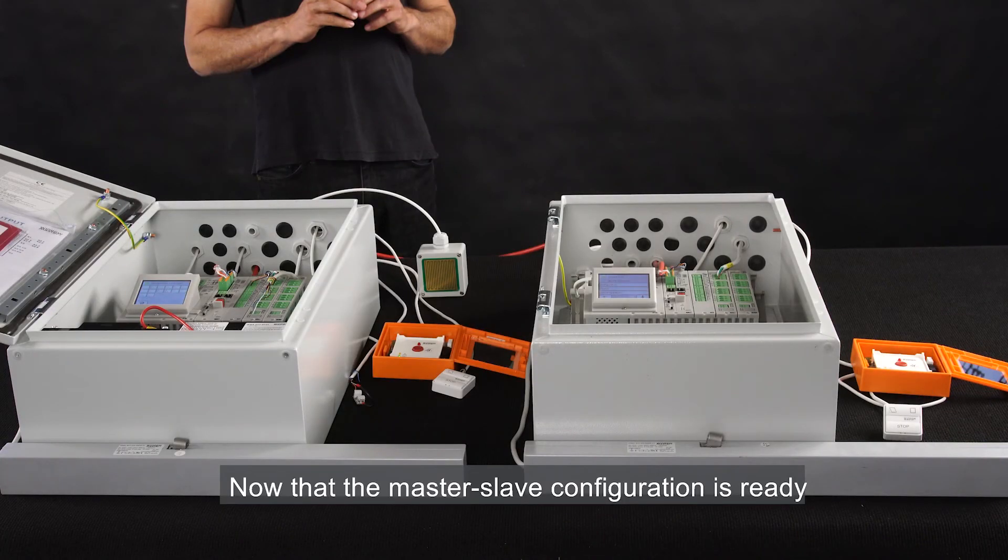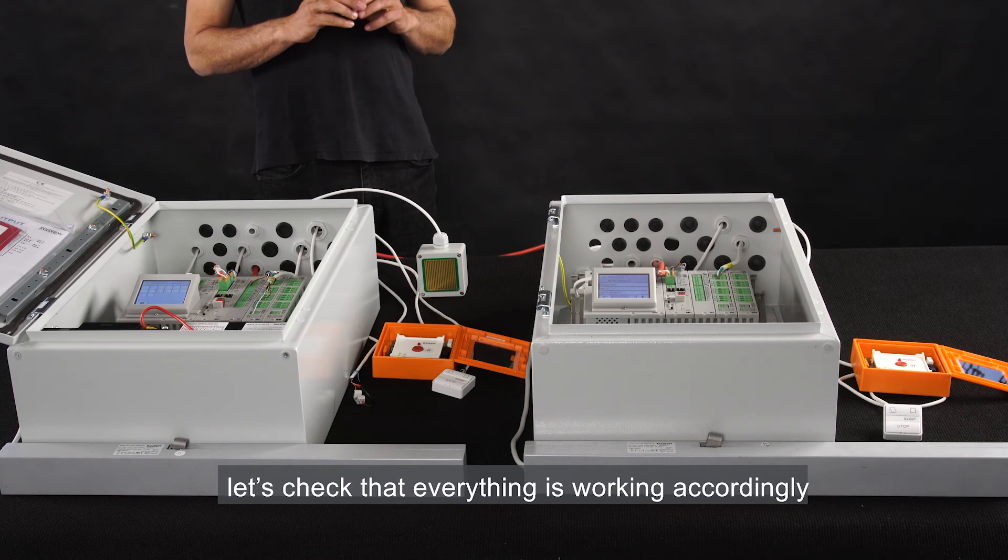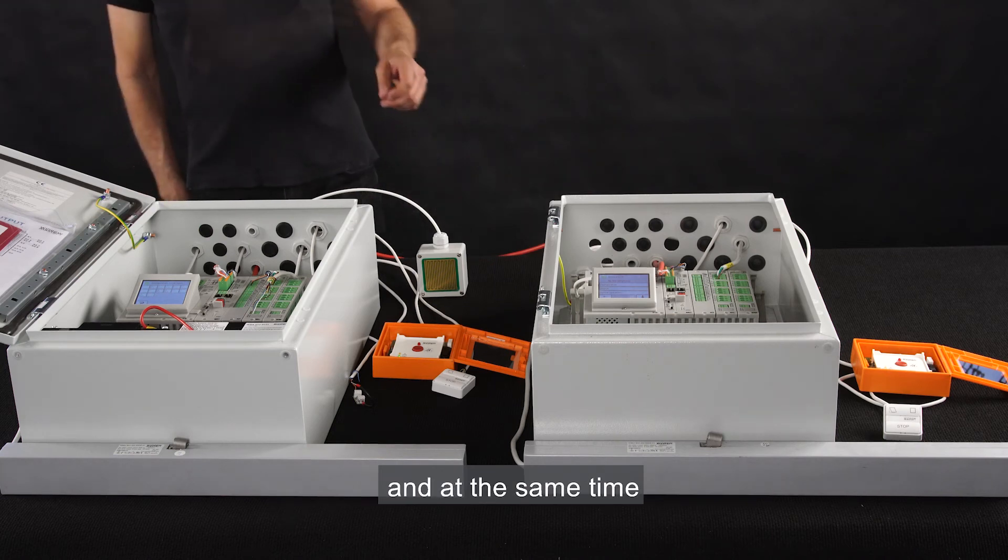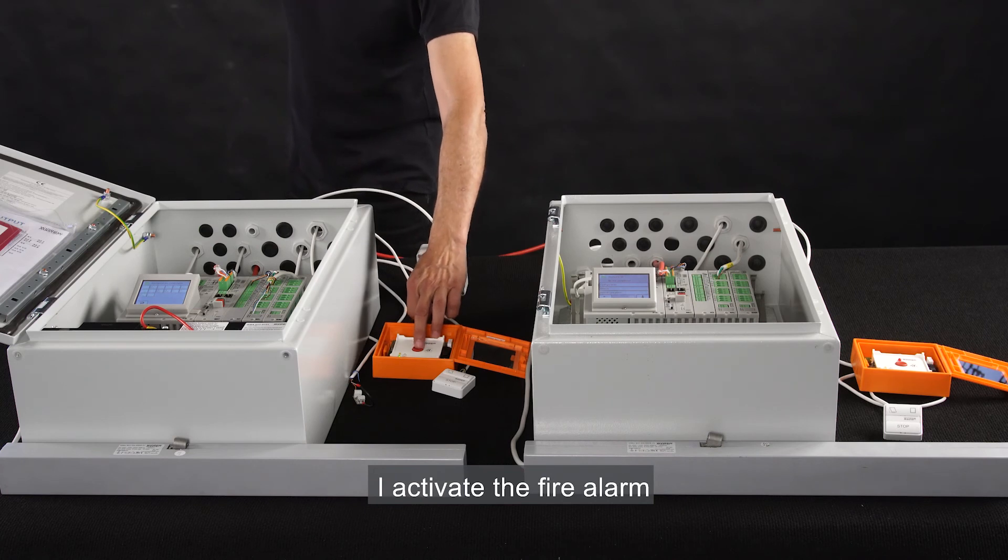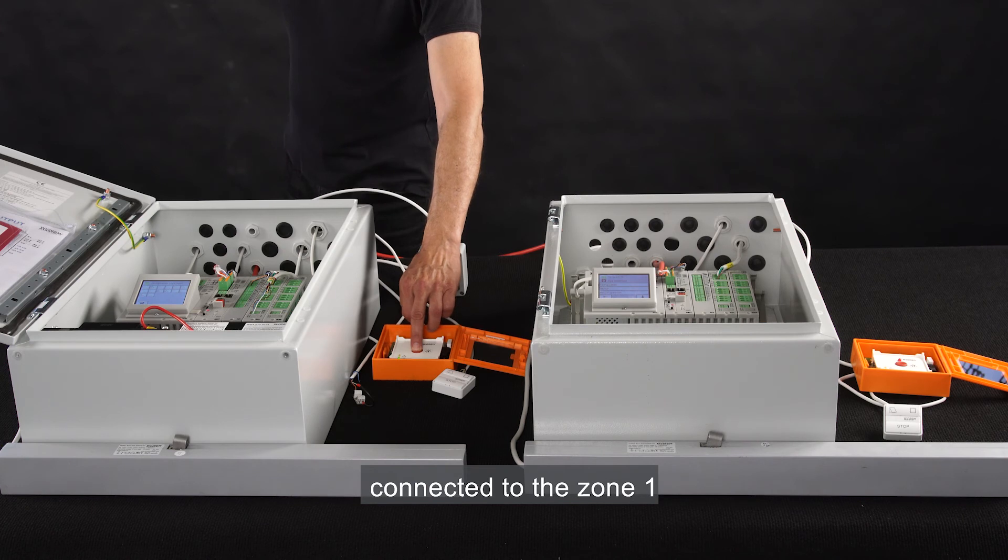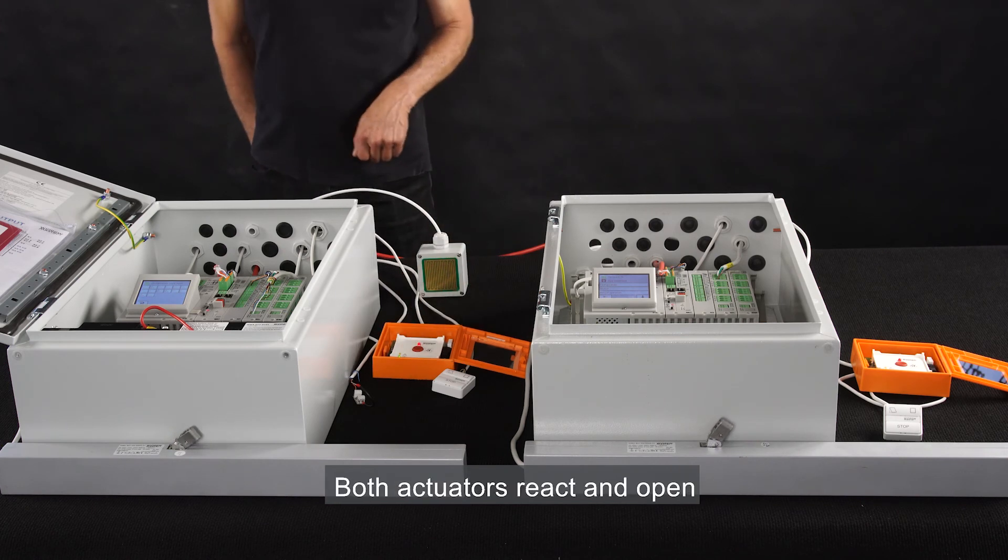Now that the master-slave configuration is ready, let's check that everything is working accordingly. If I activate one of the zones, the other one will react in the same way and at the same time. I activate the fire alarm by pressing the red button on the break glass unit connected to zone 1. Both actuators react and open, and the red LEDs on both break glass units are on.